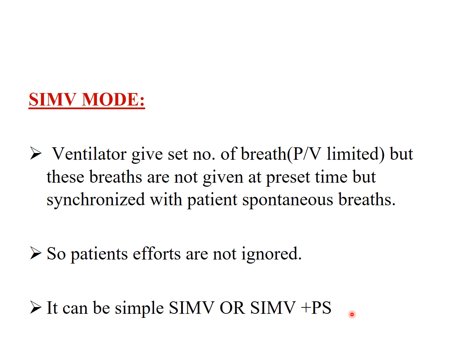This can be used standalone, or it can be coupled with pressure support. In SIMV with pressure support, the machine gives intermittent mandatory breaths which are synchronized with the patient's effort. In between, the patient is able to take his or her own breaths, but these spontaneous breaths are supported by a certain pressure depending upon your settings.